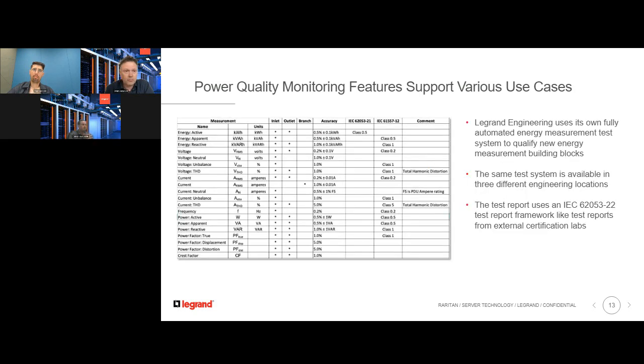Here you can see a complete overview of all available electrical measurement parameters in our PDUs. It shows the parameter units, its availability on inlets or outlets, the accuracy for each parameter, and also the relevant IEC standard behind it. We have implemented an automated test suite to qualify our metering circuitry, and this test suite is available in different locations at Legrand to ensure the highest implementation standards across all of our engineering teams. With this test suite, we are able to generate test reports similar to the reports from third-party certification labs.